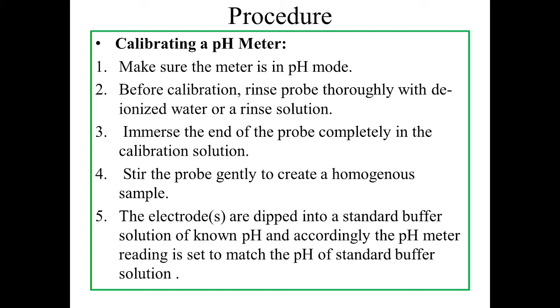Before calibration, the bottom of the probe is made up of glass. It's a glass electrode, so it has to be kept covered with a cap. So first remove the cap and rinse the probe thoroughly with deionized water or a typical rinse solution provided with the pH meter. So before calibration, remove the cap of the electrode, which is present at the bottom and covers the bulb. Rinse the probe thoroughly with deionized water or rinse solution, and then immerse the end of the probe completely in calibration solution.